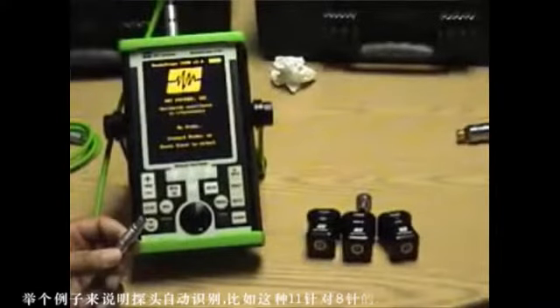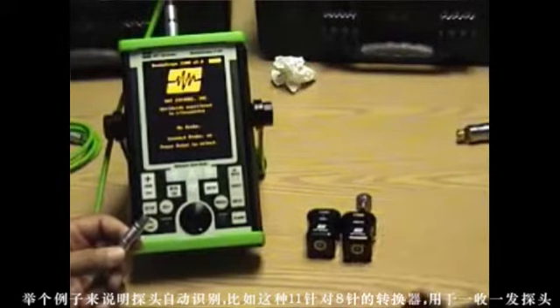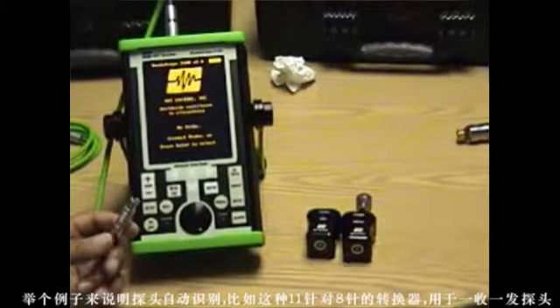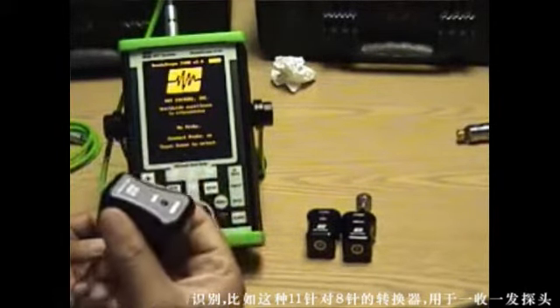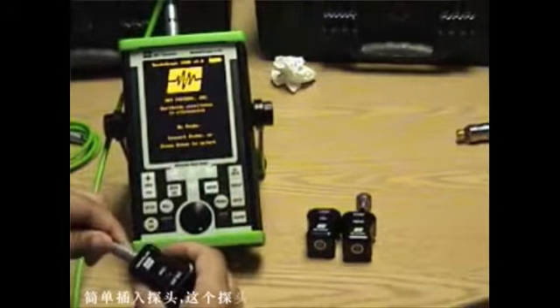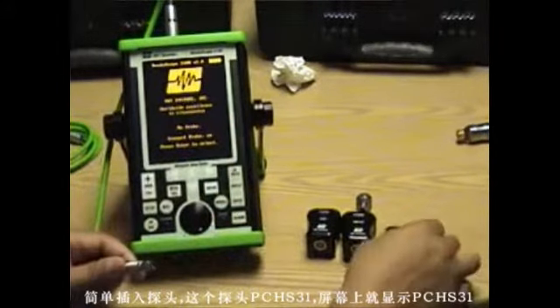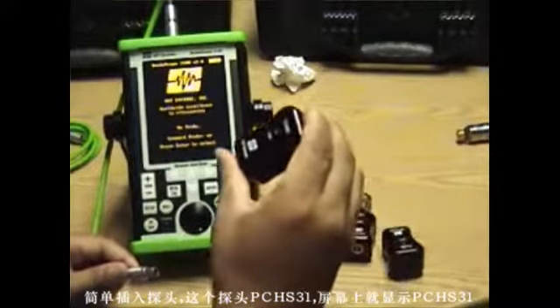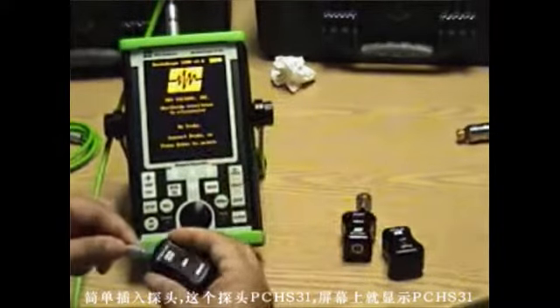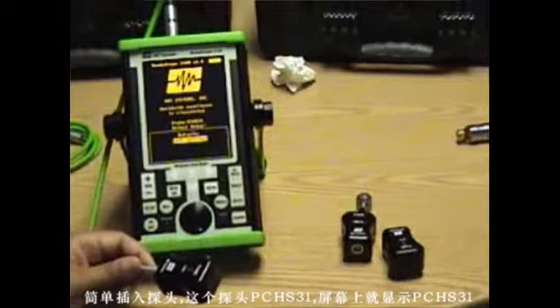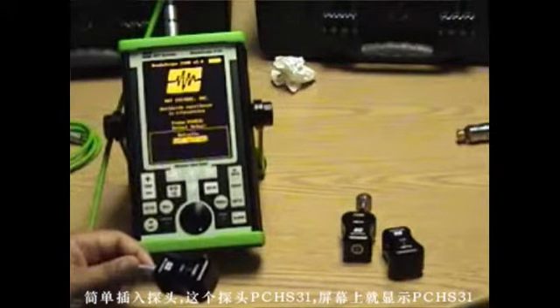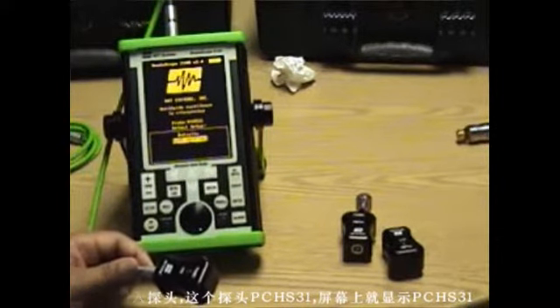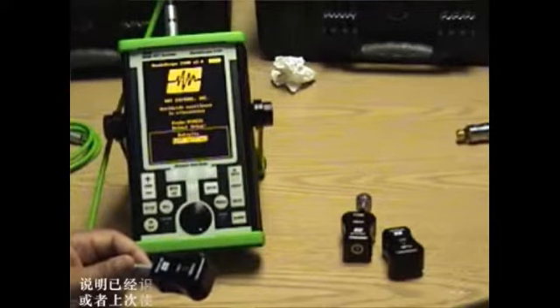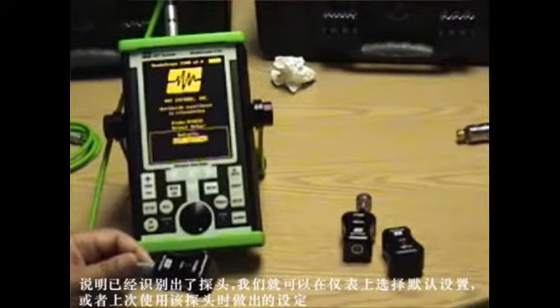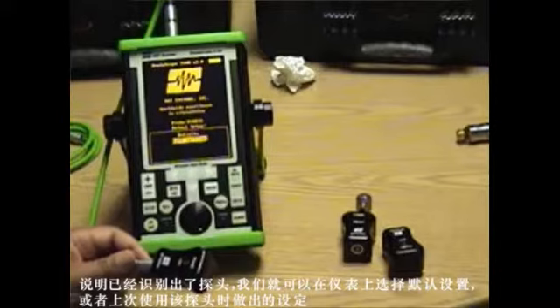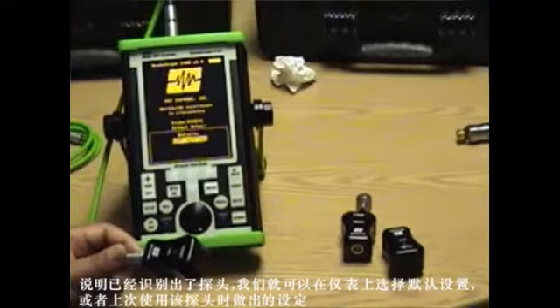Here's another example of automatic probe recognition using the 11 pin to 8 pin connector that we'll use with our pitch catch probes. By simply plugging in the pitch catch probe, this particular one, the PCHS31, it immediately pops on the screen as probe PCHS31, so the probe is recognized. It asks us to either look at the default settings or the last settings used with this probe on this gauge.